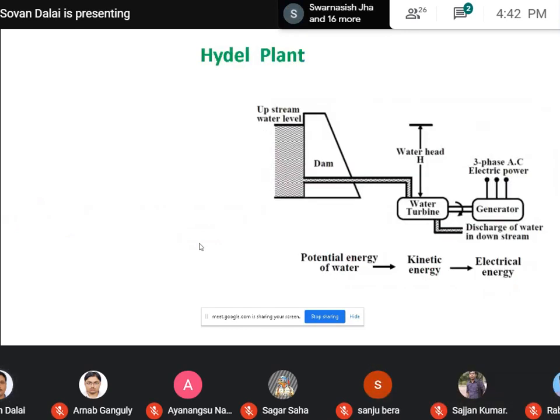Now, similar to the thermal power plant, the hydel power plant is also the same in principle. That is, the last portion, the turbine and generator portion, is the same. Only one portion is different. In a thermal power plant, the boiler passes high temperature steam to the turbine, and that high pressure steam is responsible for the rotation of the turbine. But here the principle is slightly different. We use the water head for running the turbine.